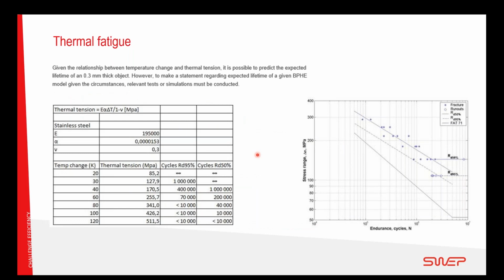When it comes to thermal fatigue, as a basis for this we're looking at the material properties. We then look at a 0.3 millimeter thick object, and that's also representing the channel plate thickness in our heat exchangers. And then we look at the temperature change and what allowed tension you can accept in the material. So we can see here that when you are above 120, the lifetime of the material is very low. It will break quite fast. And below 60 Kelvin temperature difference, when you're running a thermal shock, the lifetime is very well increased. So this is the data we have used for our thermal fatigue testing.